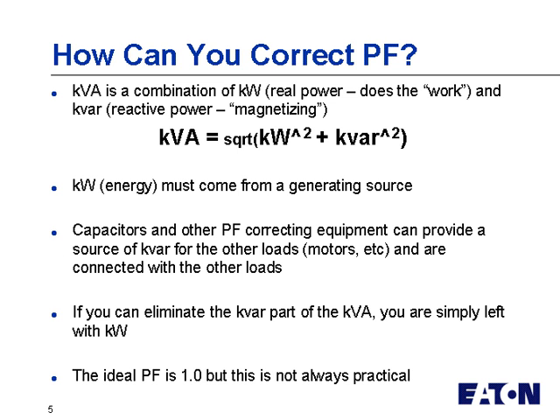Kilowatts, or the energy, has to come from a generating source. So that has to flow through the system, either from a utility or from a local generator. But capacitors and other power factor correction equipment can provide a source of kVAR locally so that you can provide that kVAR locally to the loads, and you don't need to supply that all the way back through the system. So if you can eliminate the kVAR part of kVA coming from the utility, you're simply left with kilowatts, which really means that ratio on the previous page is 1, and that you're very efficiently using the power from the utility company.